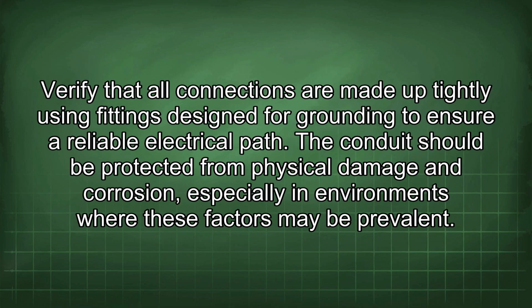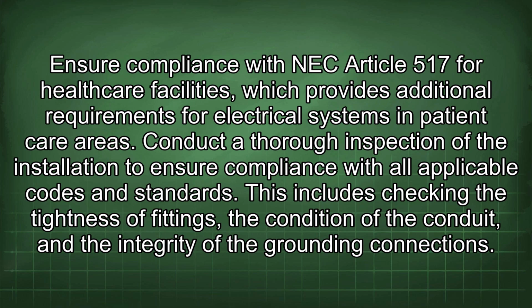Verify that all connections are made up tightly using fittings designed for grounding to ensure a reliable electrical path. The conduit should be protected from physical damage and corrosion, especially in environments where these factors may be prevalent. Ensure compliance with NEC Article 517 for healthcare facilities, which provides additional requirements for electrical systems in patient care areas. Conduct a thorough inspection of the installation to ensure compliance with all applicable codes and standards. This includes checking the tightness of fittings, the condition of the conduit, and the integrity of the grounding connections.